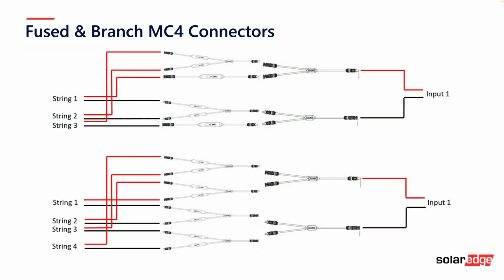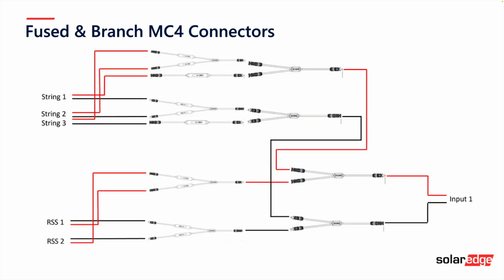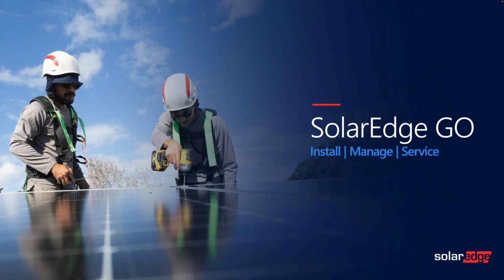Between now and summer we'll also be bringing fused branch connectors to market. This gives tremendous flexibility for combining strings, whether 3 or 4, with a standard consumable fused branch connector, or if combining multiple strings with batteries, you can do it all with the same products. They rest inside the fast mount, making it super quick and easy to mount the equipment on the wall, combine your DC in a compliant way, and bring a single port into the inverter to get the job done. Installability enhancements don't stop there.